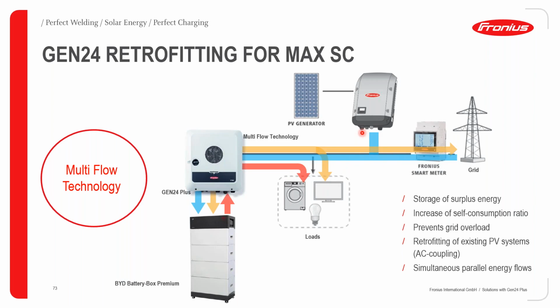One thing to mention is that once you do an AC-coupled installation with a Gen24 Plus and other Fronius Snap inverters, if there's a grid failure and the Gen24 needs to enter full backup mode, it will increase the frequency such that the other Fronius inverters in the installation switch off.